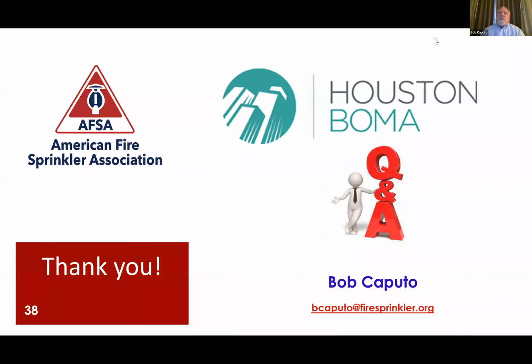So if you've got flammable liquids that are in open use, then you know you have vapors, and those vapors are going to travel along the floor. If somebody has shoes with a nail in them and they make a spark by hitting that on the concrete, you could have an explosion in that area of your building. So you're going to have intrinsically safe electrical outlets and lamps and lights and a whole bunch of other environmental controls than if you're just moving stuff around in 55-gallon drums that you're storing and reselling. So it's a very, very complex question, but I hope I've chewed around that enough to give you a sense of the need there.